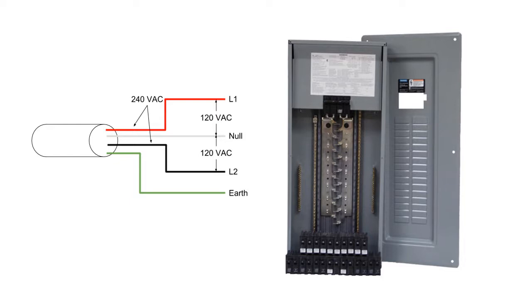L1 and L2 are then wired to power a section of the house such as a room or a specific appliance. The connections are fed through breakers that limit the current in case of faulty wiring. Breakers typically come in 15 and 30 amps. However, there are several different values that could be used, which is a topic for later. The nulls or returns and ground wires from all the household loads are connected to a bus bar in the panel, thereby grounding the entire box.